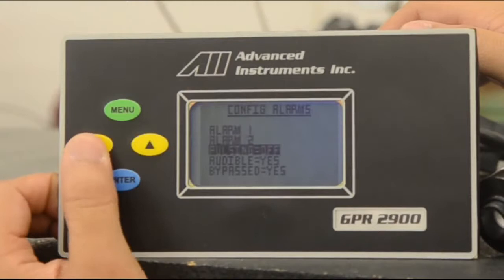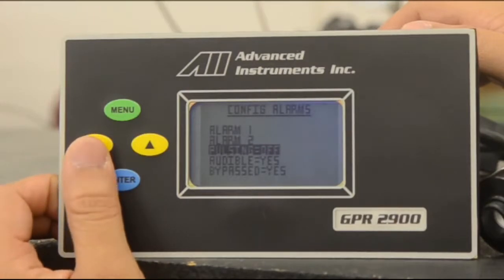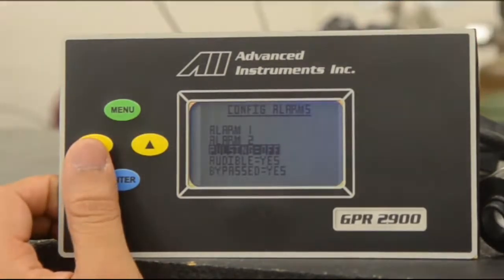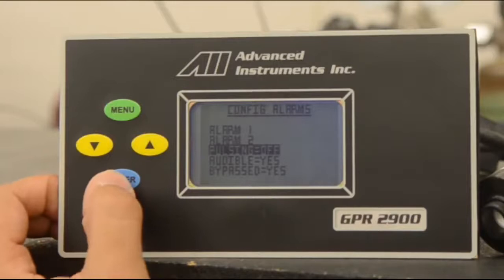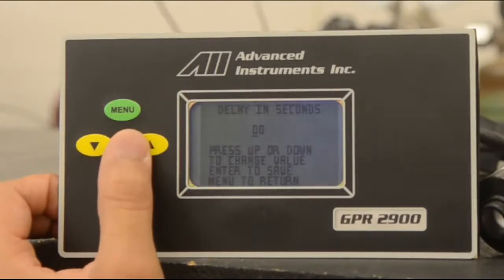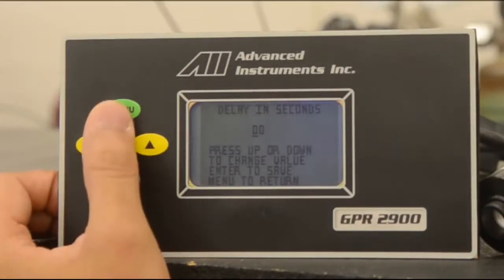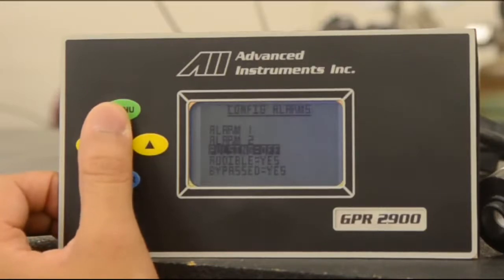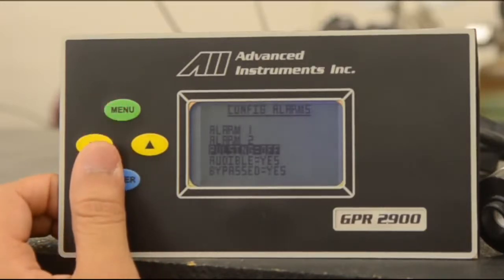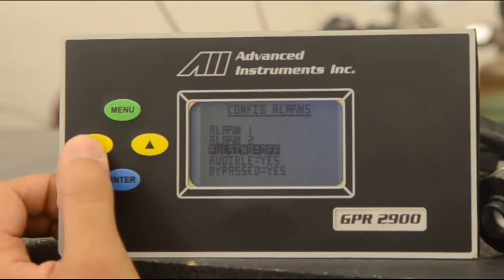You also have the option of pulsing, which essentially, if you are tied into a system that is low powered and you only want to send a pulse signal, you hit enter and set your delay value. That will configure the alarms to pulse for that amount of time and then de-energize.